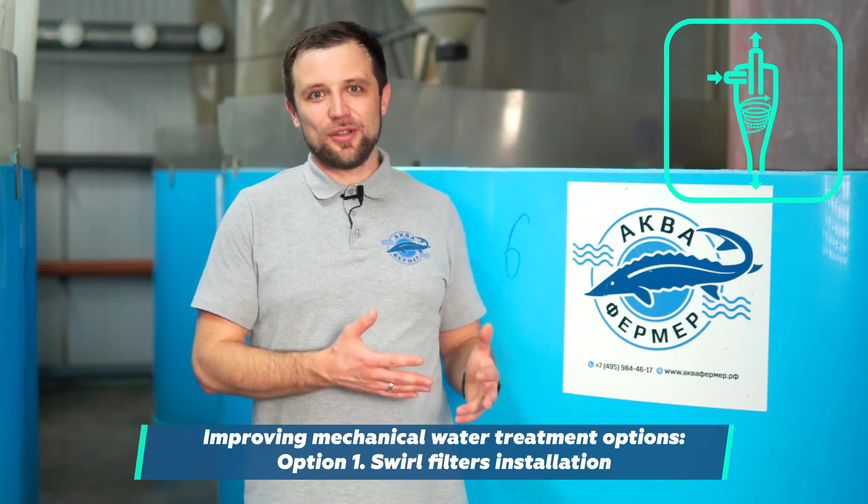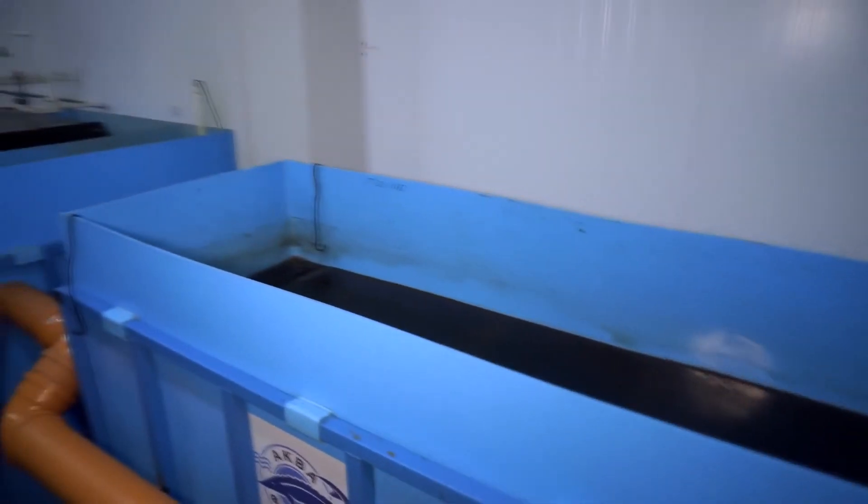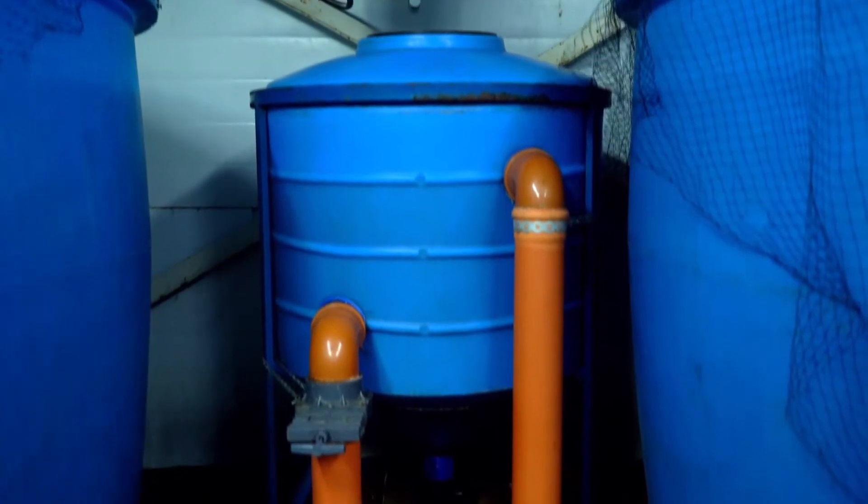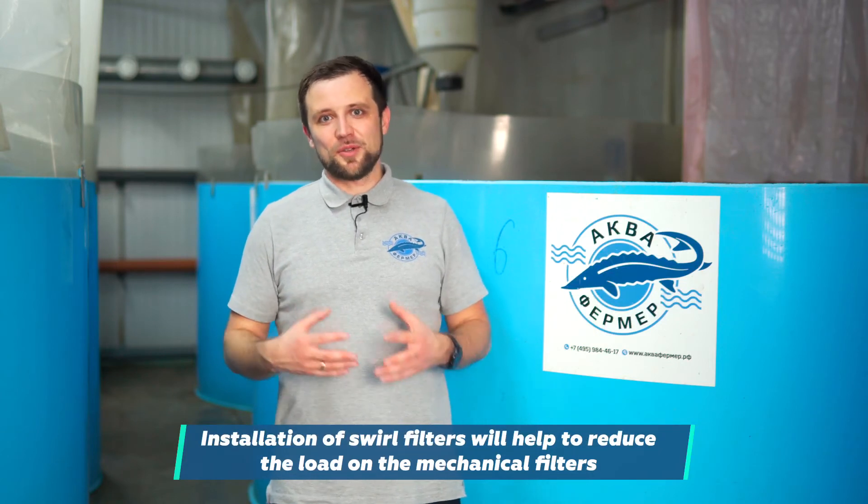Let's sort out the mechanical water treatment issue first. We discussed everything with the owner, as there are several options to prevent problems in the future. The first option is to add swirl filters connected to the tanks. Right now there is a side drain from the tanks and the water flows directly to a thin layer settling tank where the coarse suspended solids are sedimented. Swirl filters are tanks with a conical bottom in which water moves in a circular mode — all coarse suspended solids fall to the cone bottom and filtered water is discharged from the top. Swirl filters trap suspended solids and alleviate the load on mechanical filters.